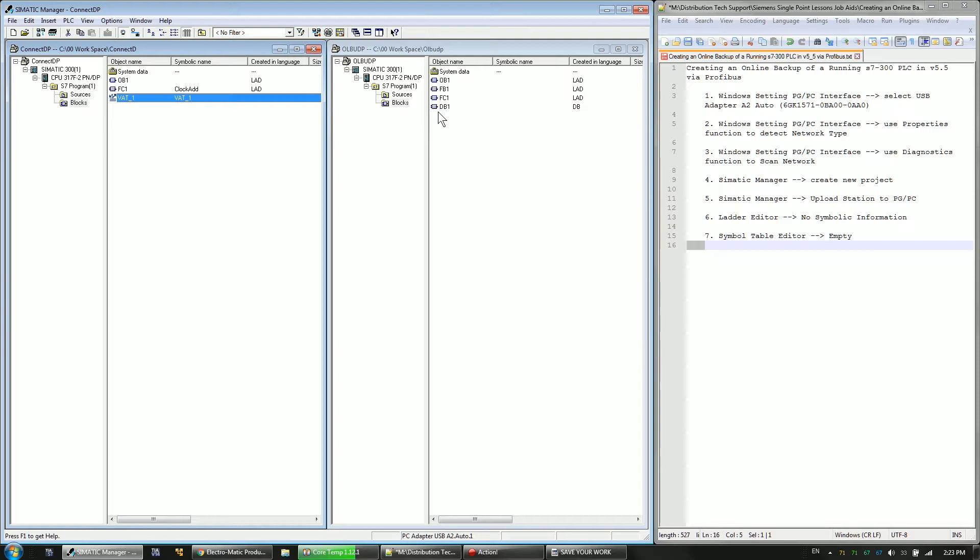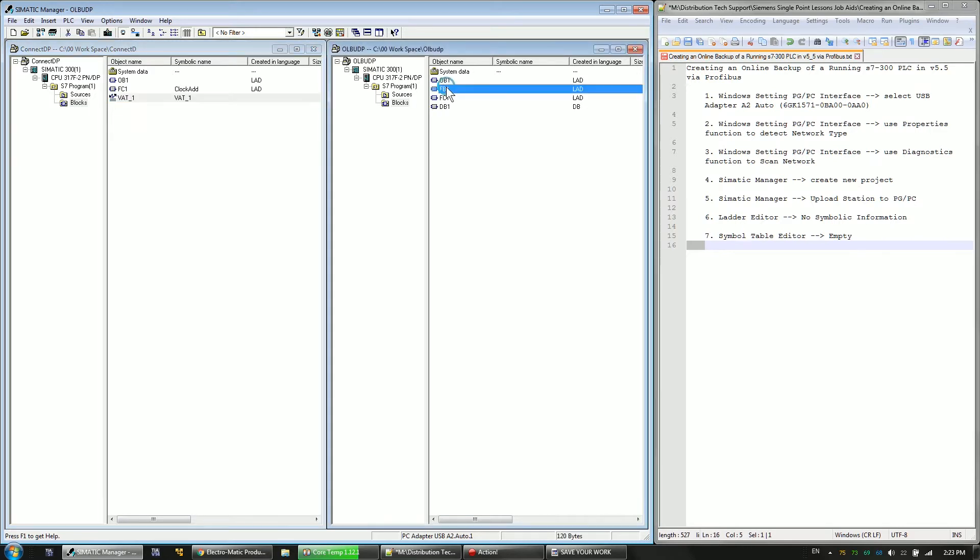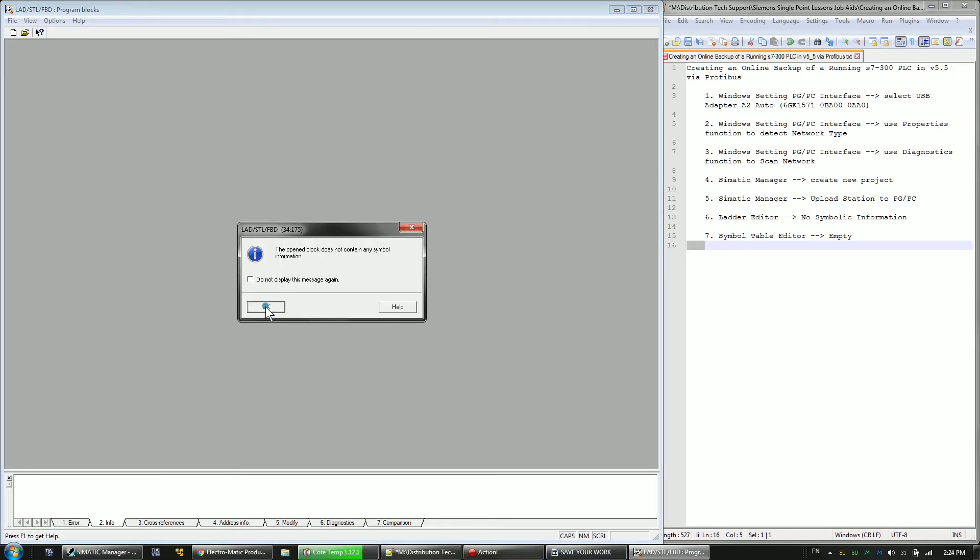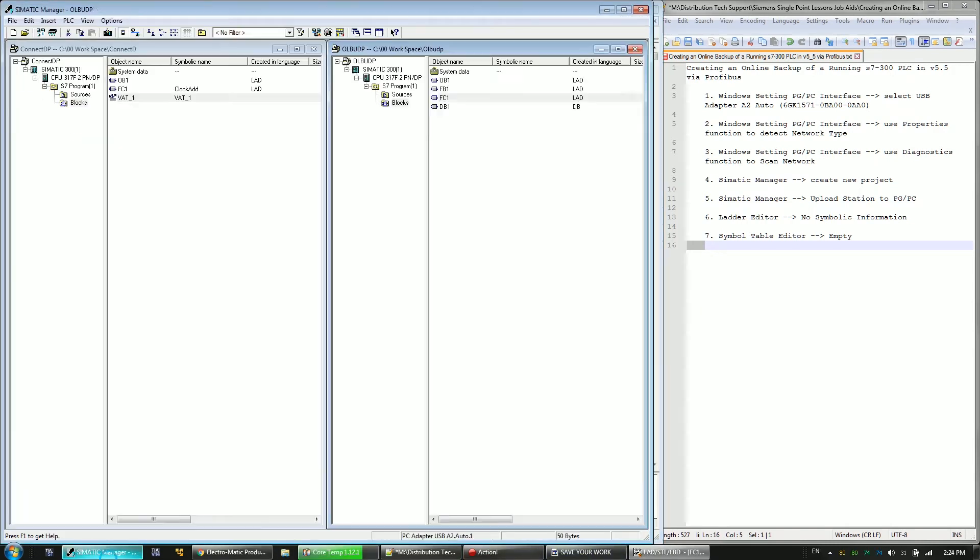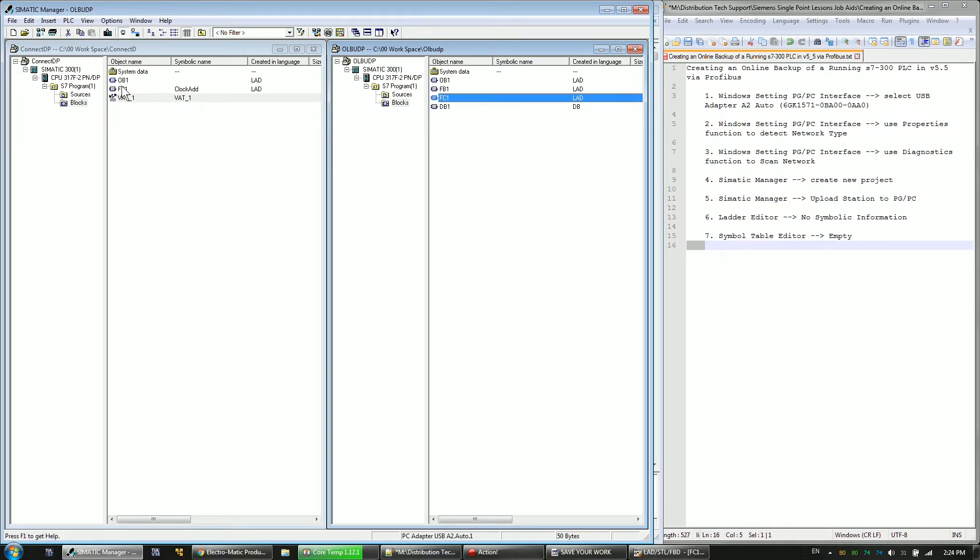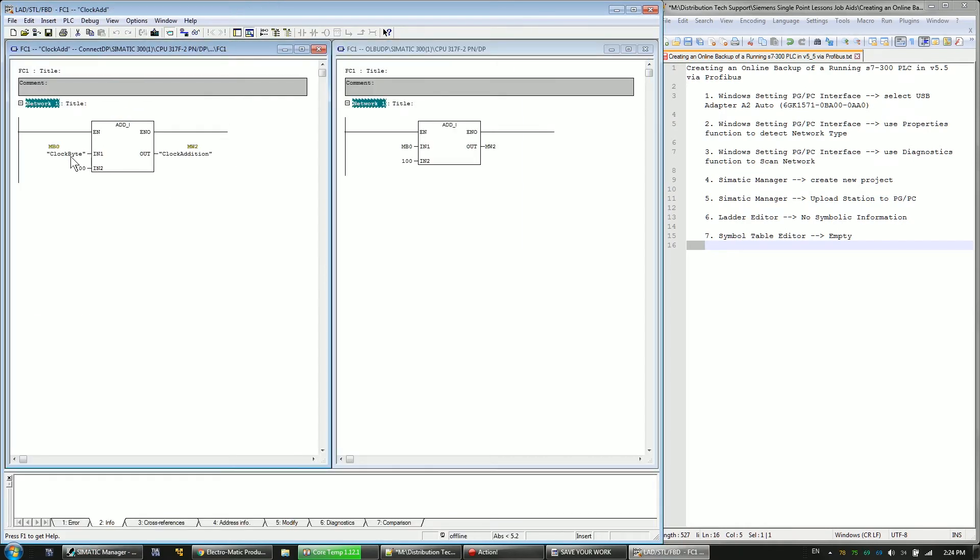And also, there's no symbolic information. So, no variable table. If I go inside of FC1 and I come back out to here and open up FC1 here, we can look at them side by side. And as you can see, I've got symbolic names for my memory byte 0 and memory word 2 here that aren't there.